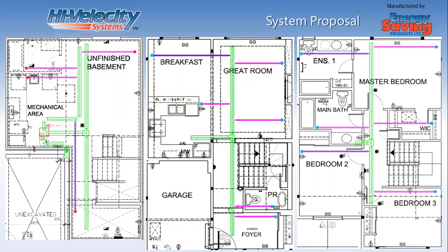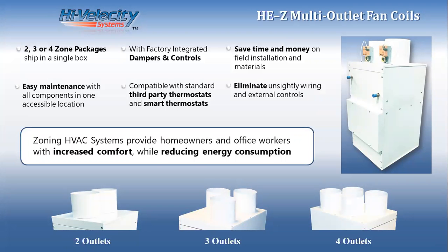zoning criteria. But having that thermostat per floor also provides numerous efficiencies rather than running the equipment at 100% all the time to meet a small demand. We can operate at 1/3 or less, depending on how we're designing that zoned duct system. We even fit our equipment at the factory with dampers and zone controls to make it simple and easy in the field for our customers to install these systems. So it comes with the damper and zone control. You run an independent duct to each area, and off of that independent duct, one thermostat will provide the demand to turn on and turn off the system based on the occupant's requirements.